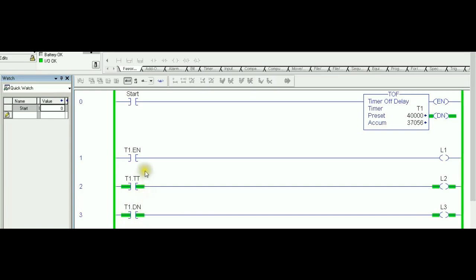By no chance can the TT and the done bit both be on at the same time in TOF. Only with the accumulator has the preset value, that's when both these parameters go to zero and both lights go to zero.